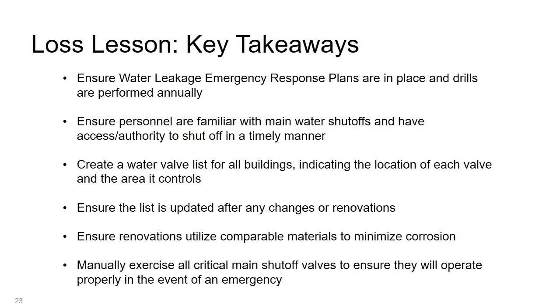Now we'll touch on some of the key takeaways from this loss. The most notable lesson I wanted to highlight here is that personnel on all shifts should be familiar with the location of these critical water shutoff valves. We see all too often that the main facilities personnel or plumbers are familiar with the locations, but that off-shift or backup personnel may not be fully aware of the building features. By running through mock scenarios ahead of time, the duration of water flow in this case could have been reduced from 90 minutes down to under 30 minutes.